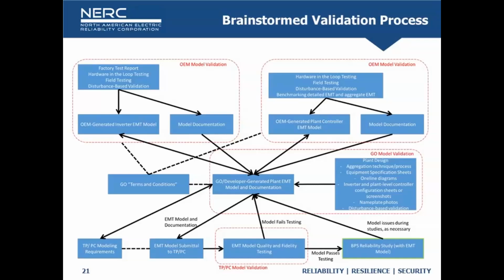So when they provide a model, they should have some documentation that it's valid in some way. Now, some OEMs may not do factory testing, some may not do disturbance-based validation, some may not do hardware-in-the-loop testing. But they should have some form of validation to say: the way I came up with this model, I believe it, I certify it is valid, that it matches a specific make, model, software version of equipment installed in the field, and the settings match what's expected out there.